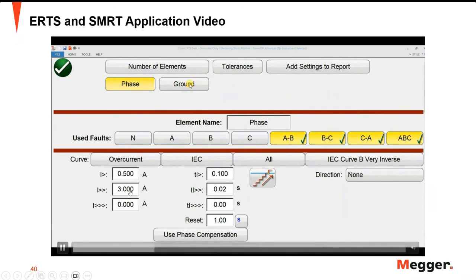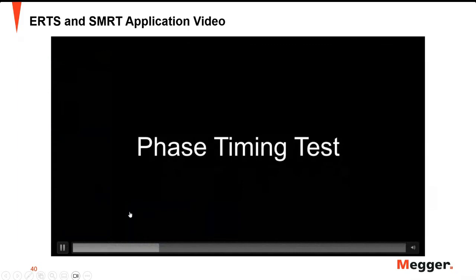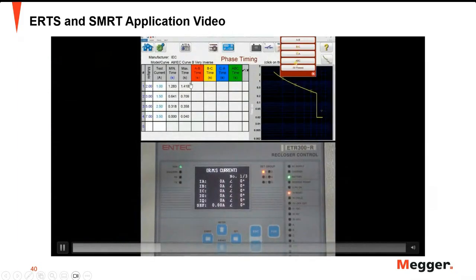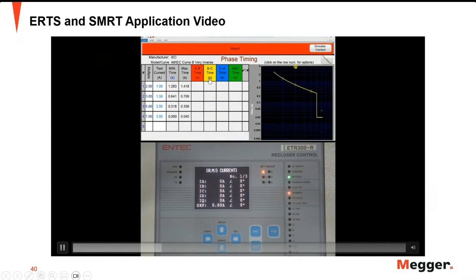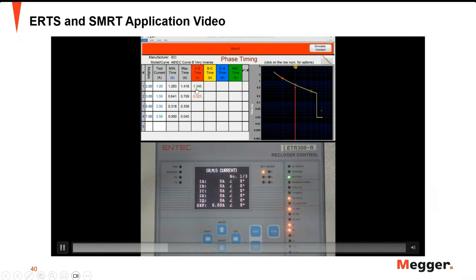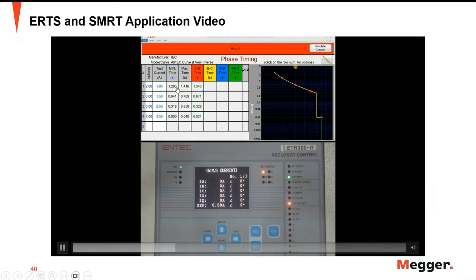The instantaneous settings is 3000, and for the ground settings, this is your pickup and the instantaneous ground. For the phase timing test — phase AB, phase BC, phase CA, and three-phase ABC — this is the result for AB at two times your settings: 0.5 times 2, so this is your test current of 1 ampere. This is your minimum and maximum time, or the allowable range.